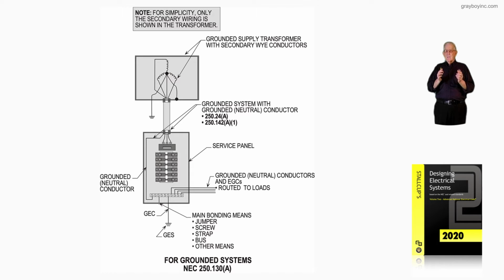So what this is pointing out: if the transformer's grounded, then the service would have to be grounded, and we would meet 250.24. We would also then comply with 250.142A1 using the grounded conductor from the transformer to the service equipment that you see. So with 250.24, we're grounding the outside transformer, and we're grounding the service equipment, and we're grounding in accordance with Table 250.102C1.